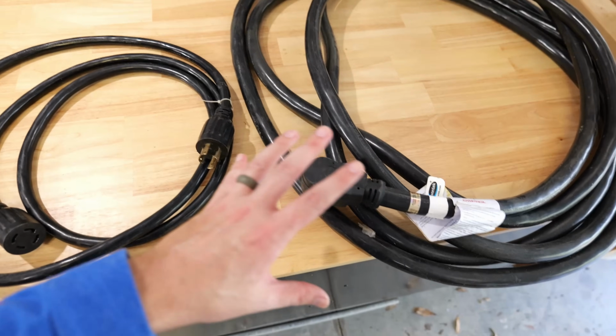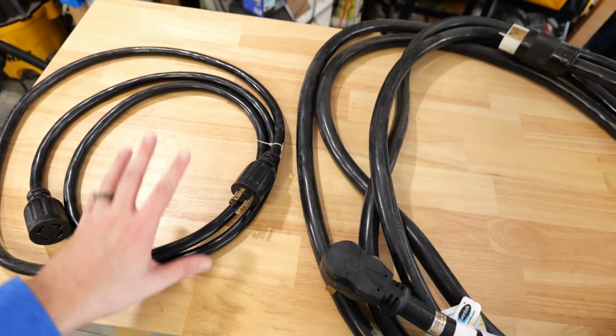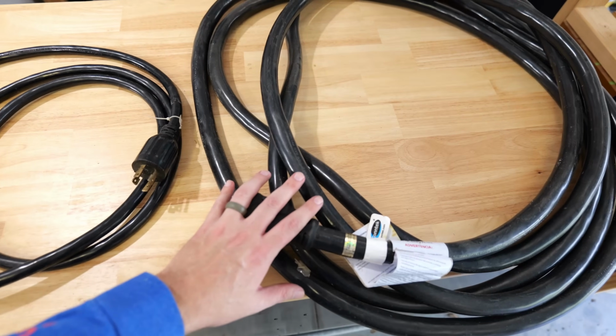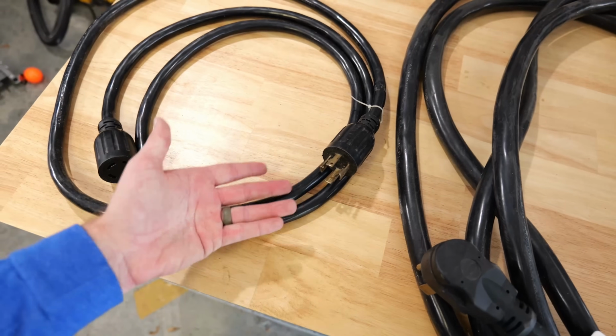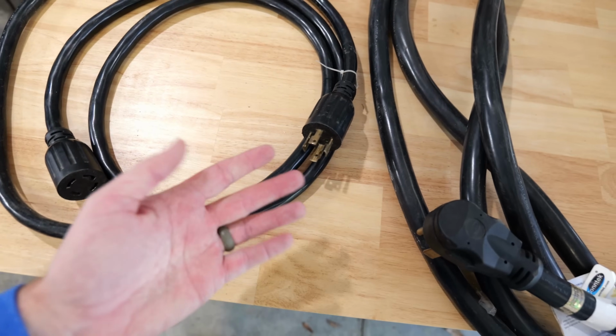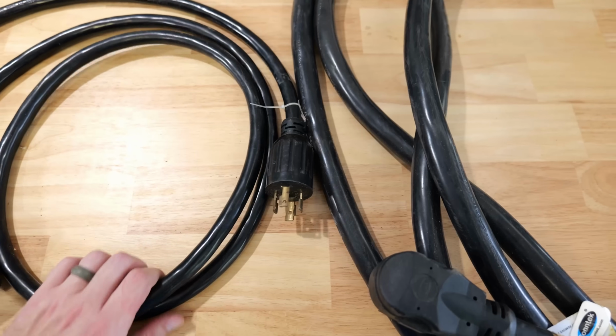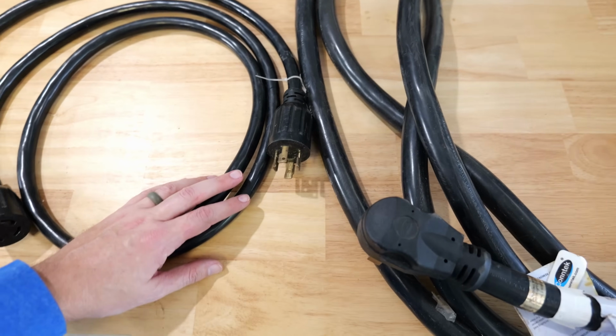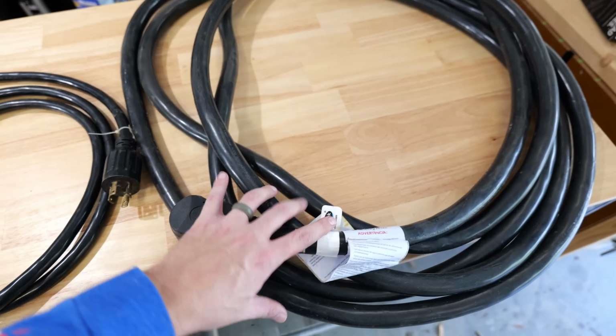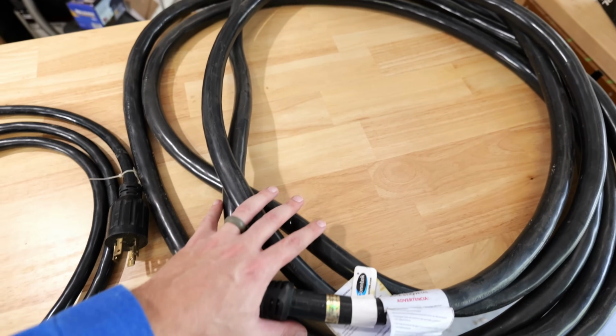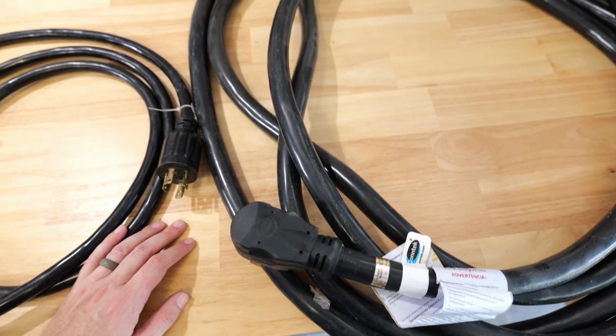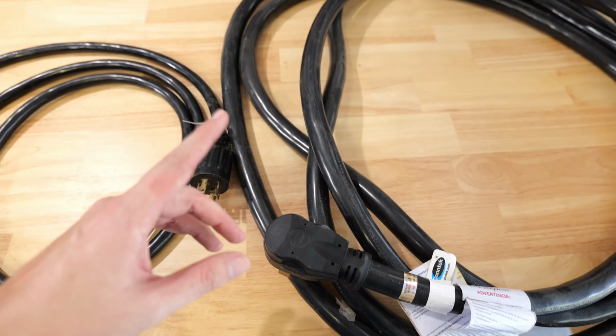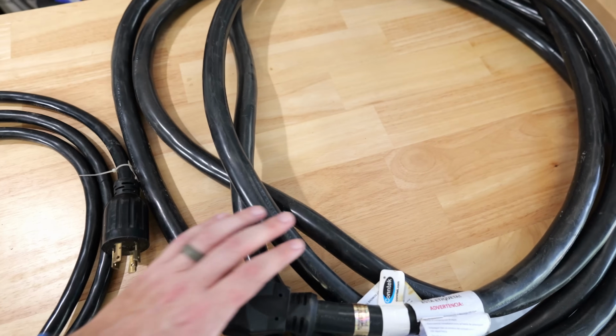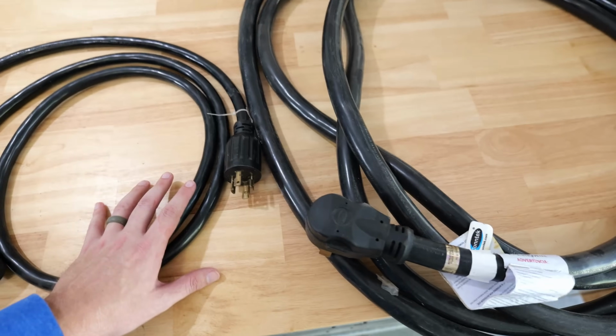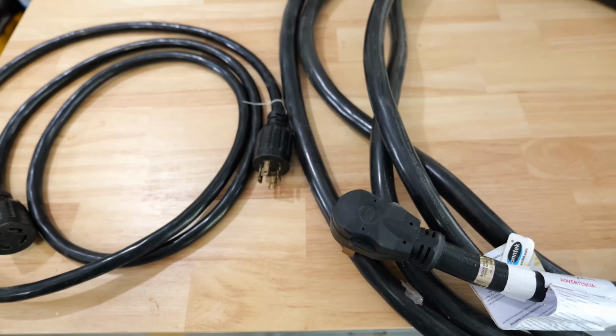So I show you all of this because there is a huge difference in getting the right materials for your particular application, because if you were to go with a cord or wiring that is too small, say you're going with a 50 amp power inlet box, and say you install 10 gauge wire into that power inlet box, but you're operating with this cord and a generator that's capable of supplying 50 amps, you're creating a serious fire hazard by having that smaller wiring going from your power inlet box to then your house. So the wiring needs to be big enough for your particular application. So now let's get into talking about that and figuring out how we know what we need.